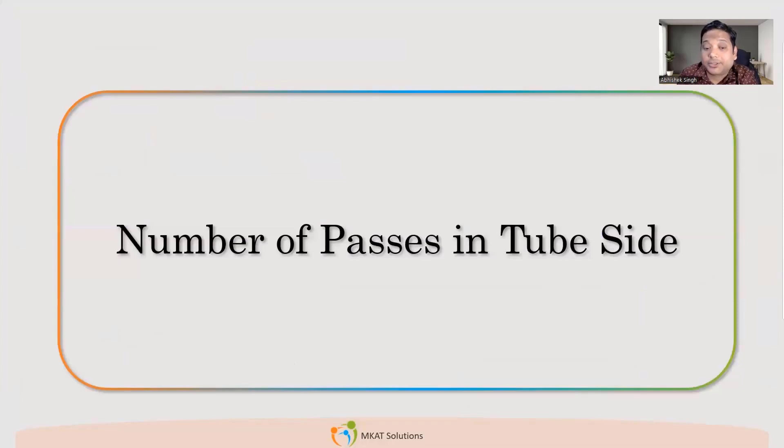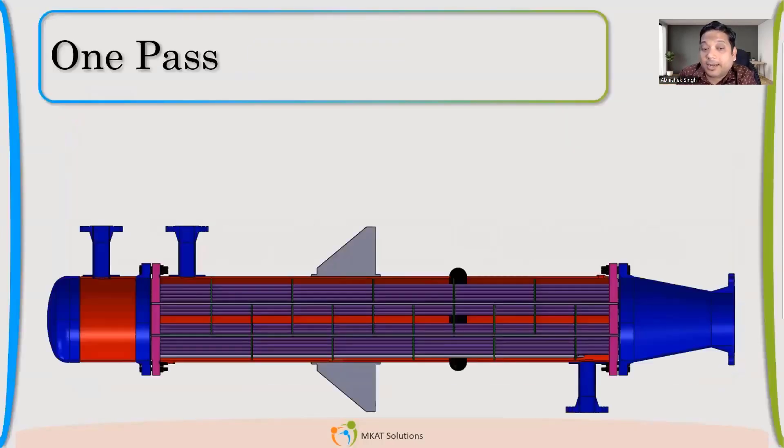Now the next part, which is number of passes. Many times we get confused with number of passes. So one pass, it's very simple. The flow will come from one side and flow like this. So this is called one pass. We are talking about passes in tube side. When your fluid in tube side will pass only once in the shell, it is one pass.